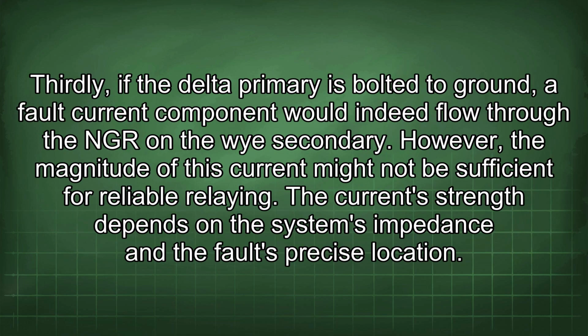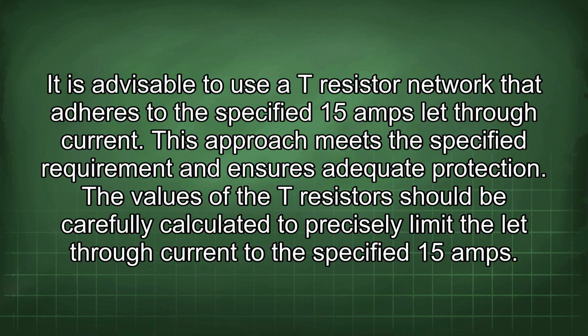Thirdly, if the delta primary is bolted to ground, a fault current component would indeed flow through the NGR on the Y secondary. However, the magnitude of this current might not be sufficient for reliable relaying. The current strength depends on the system's impedance and the fault's precise location. It is advisable to use a T resistor network that adheres to the specified 15 amps let-through current. This approach meets the specified requirement and ensures adequate protection.